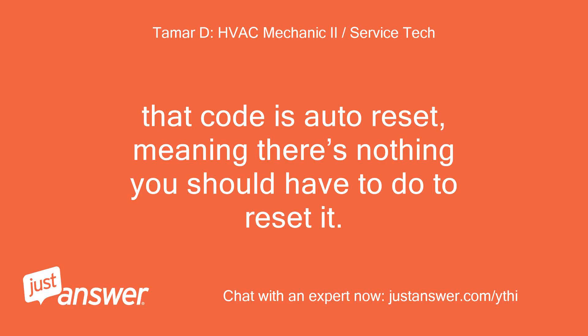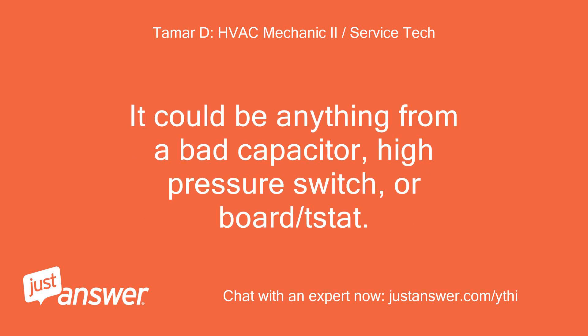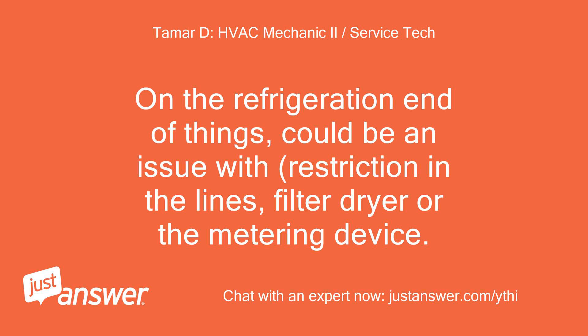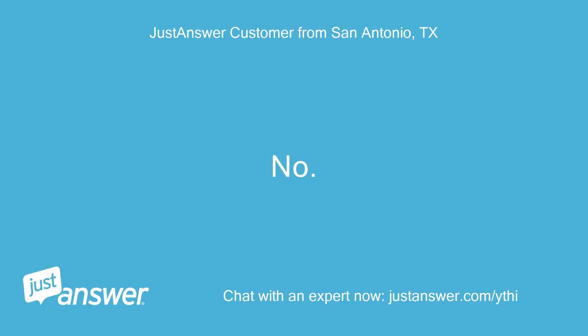That code is auto-reset, meaning there's nothing you should have to do to reset it. Basically it's saying the internal pressure of the machine is abnormally high — this information may be correct or incorrect depending on whether the sensor or board is bad. It could be anything from a bad capacitor, high-pressure switch, or board/tstat. On the refrigeration end, there could be a restriction in the lines, filter dryer, or the metering device. Do you have a multimeter that can read capacitance? No, I don't.